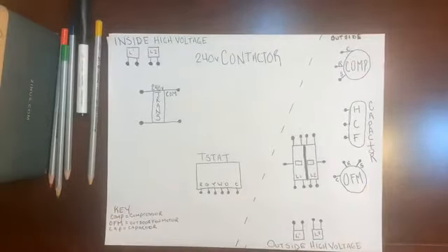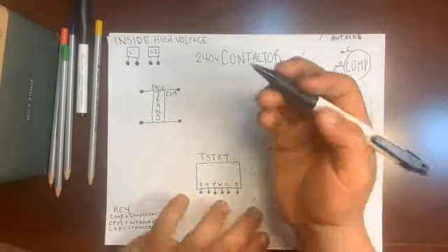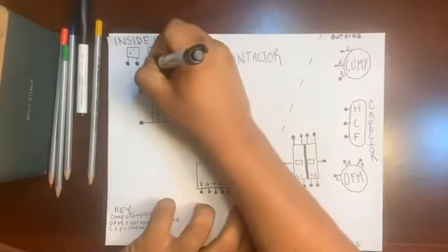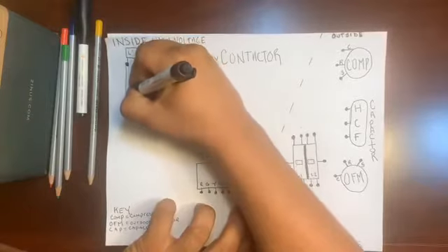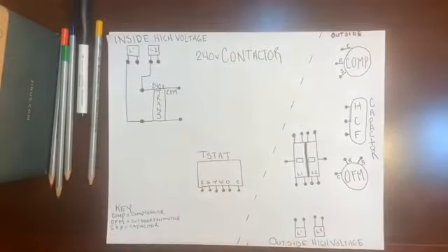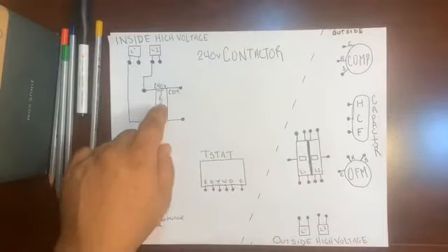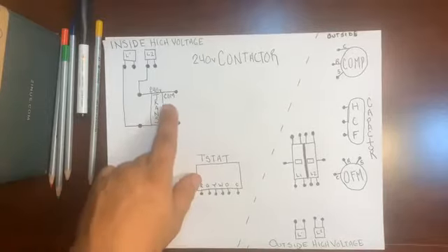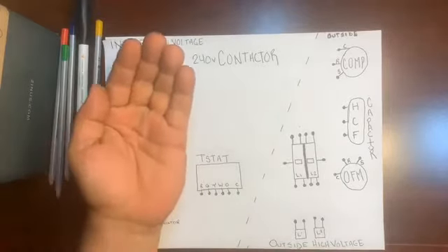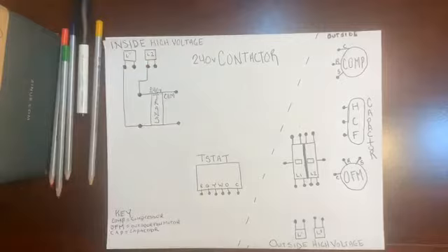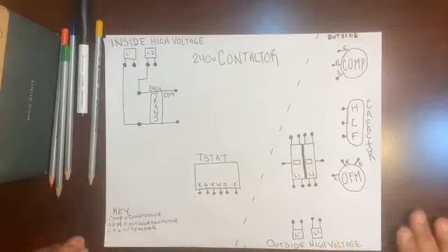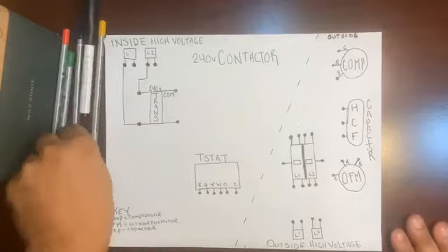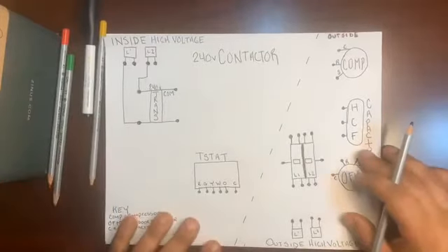So let's go ahead and start with the basics. We'll go back to our transformer. See L1, L2 on the primary side. We're gonna take L2, bring it down, bring L1 down, and provide our transformer 240 volts, and then pick up 24 volts on the secondary side with our common wire. Put the common in my hand, we'll start with that notion. Okay, so looking at all these connections, you think, hey, that's a lot, where do I start? Start with our high voltage, and then we'll start with first things first, our common.